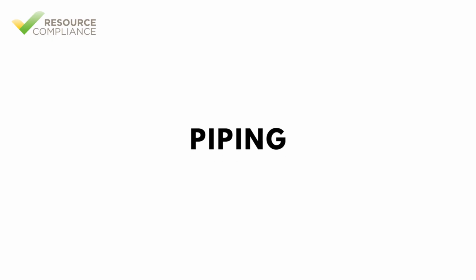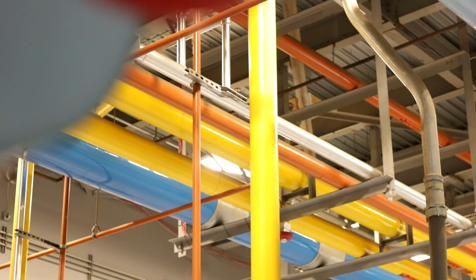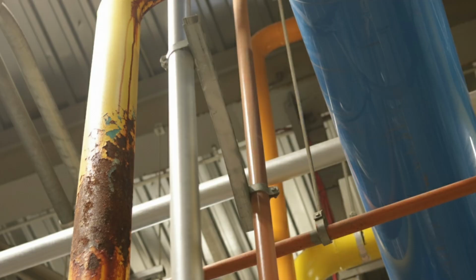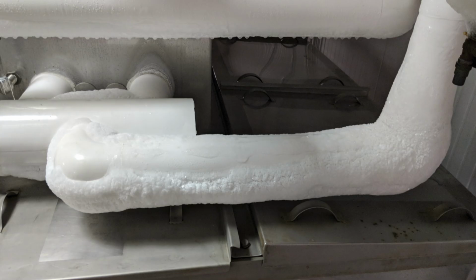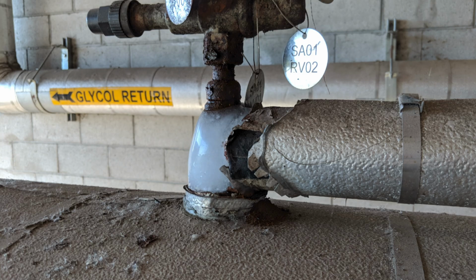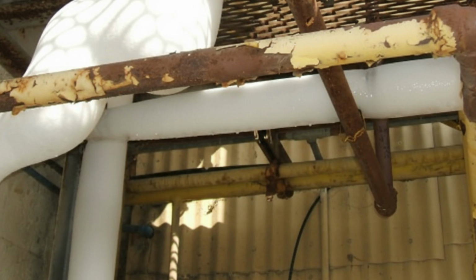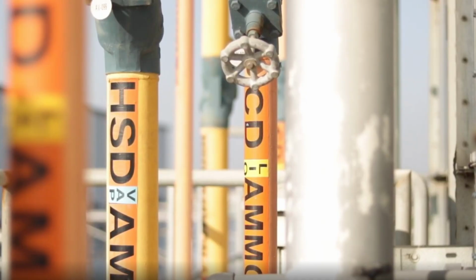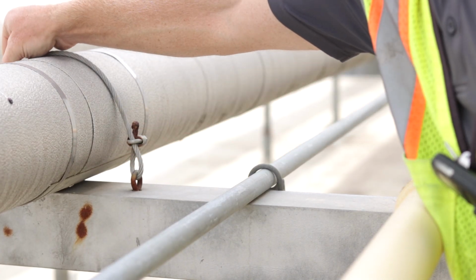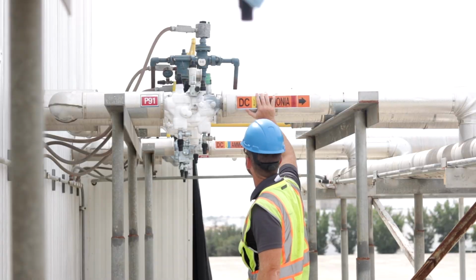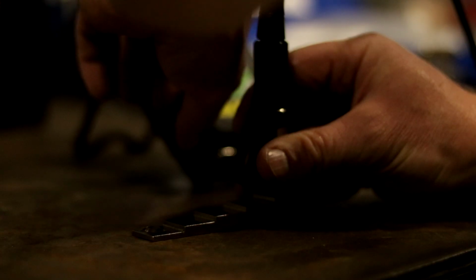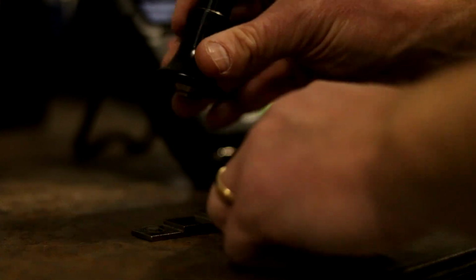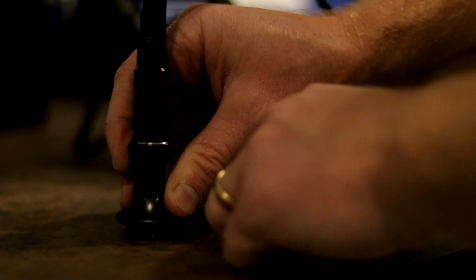Like pressure vessels, refrigerant pipes must be inspected annually. During the inspection, the inspector will look for surface corrosion and pitting, moisture in the insulation that could lead to corrosion under insulation, damage to an insulated pipe's protective jacket, paint degradation, proper pipe labels, adequate piping support, including sway braces, and excessive vibration. Every 5th year, ammonia piping should be assessed by a qualified inspector to determine if non-destructive testing, or NDT, should be performed.